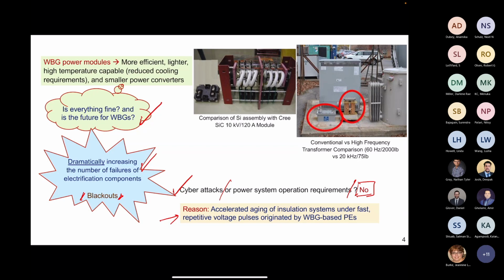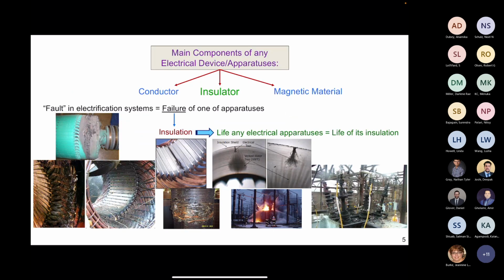So when we talk about a failure, I have some pictures of the failure of the power system equipment here. When we talk about a fault in a power system, this is often related to the failure of the insulation of an apparatus, and not, for example, failure of the conductor or magnetic material. So here I can make a statement: the life of any electrical apparatus is determined by the life of its insulation. So, most of the time.